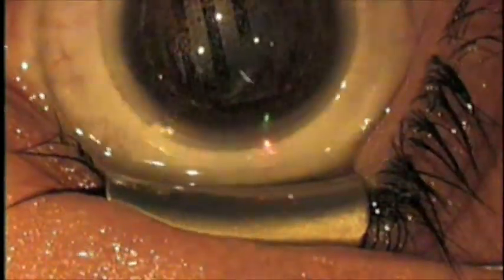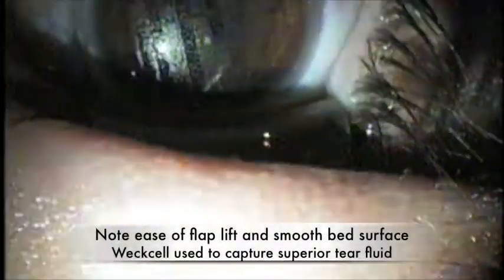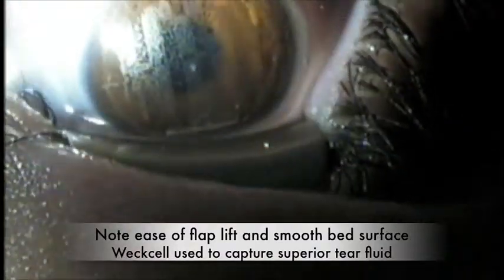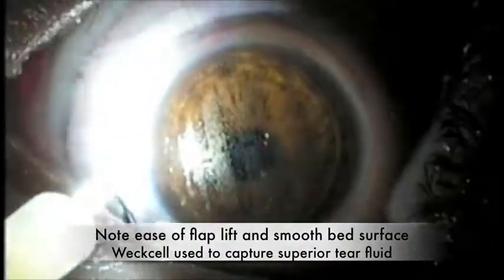The main thing is that we get these very consistent, very low standard deviation flaps, with an extremely reliable device. This device is a solid-state laser — it doesn't have all the amplification and all the complicated optics. The result is that the device can be serviced. In fact, you can even buy a service contract which services the laser over the Internet.